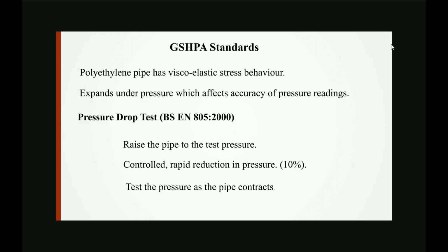Now, polyethylene pipe is a substance which suffers from viscoelastic stress. We also call that creep. So it expands under pressure, and when it does that, that affects the readings that you take. So the GSHPA have borrowed a standard, a British and European standard, BS-EN 805, which has been around since 2000, and that's a test for installing water pipes. That's also subject to viscoelastic stress, and it's been around for 24 years, and it takes into consideration the fact that when you increase the pressure, the pipe expands.